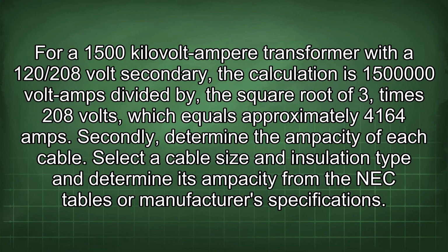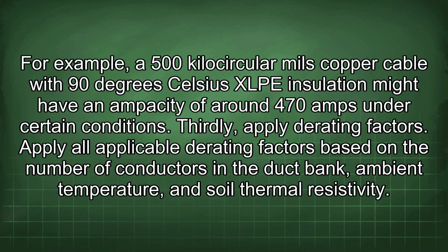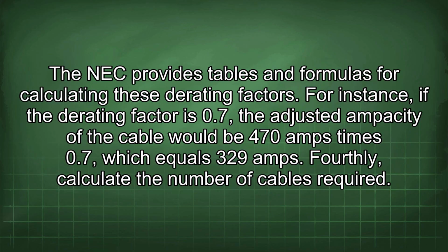Secondly, determine the ampacity of each cable. Select a cable size and insulation type and determine its ampacity from the NEC tables or manufacturer's specifications. For example, a 500 kilocircular mils copper cable with 90 degrees Celsius XLPE insulation might have an ampacity of around 470 amps under certain conditions. Thirdly, apply derating factors. Apply all applicable derating factors based on the number of conductors in the duct bank, ambient temperature, and soil thermal resistivity. The NEC provides tables and formulas for calculating these derating factors.